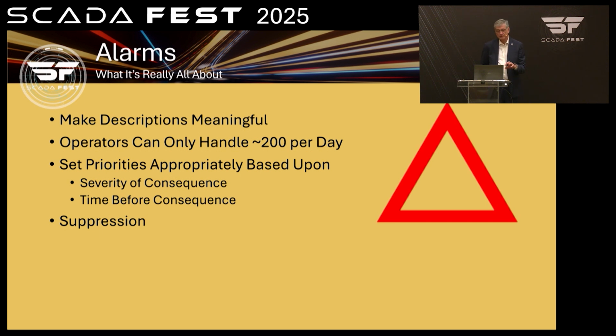So let's take a look at one of my favorites, a low flow alarm. You can put a low flow alarm in, but if the pump is off, that low flow alarm is a nuisance. Of course there's a low flow, the pump is off. So the low flow alarm should only be working when the pump is on. You make that consequential alarm conditional so you don't get these nuisance alarms every time the pump turns off and I get a low flow alarm. Of course there's a low flow, there's no pump running. Get that 200 a day down.